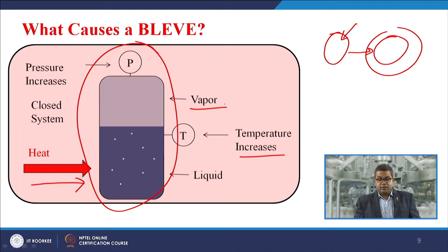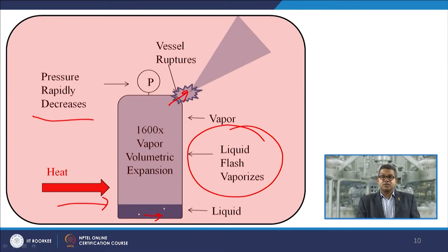Since pressure increases rapidly and heat is continuously added, there may be volumetric expansion of the vapors, and the liquid is just above its boiling point. So almost 1600, 1700 or 1800 times volumetric expansion may be experienced, and at this point the vessel ruptures. The liquid inside, because it is at a higher temperature as well as pressure, flashes, and all the flashed vapors tend to escape to the atmosphere.